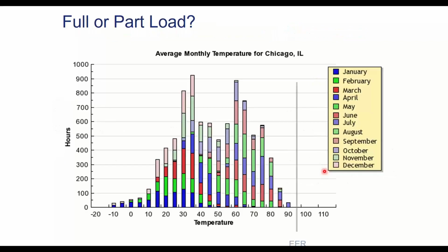So the reason why we're focused on part load instead of full load is essentially full load never happens in real life. I mean, it just doesn't. If you perfectly designed a system so it exactly matched the load of your building, which nobody does, everybody oversizes. But if you did that, the EER test is done on a 95-degree day. So when it was 95 degrees outside, which is hotter than a normal day in Chicago, that's when you'd be at full load. There's almost no run hours there. Like, it hardly ever happens. It's a couple blips a year.